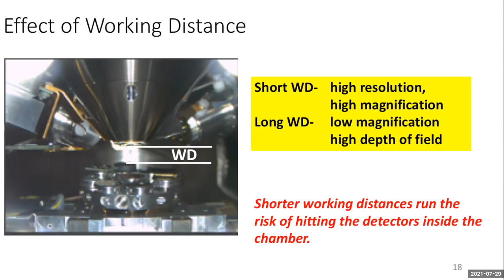However, a shorter working distance may run the risk of hitting the detectors. You can see the detectors inside the chamber of the SEM. So a shorter working distance may cause the sample to hit the detectors inside the chamber. So be careful when you work with a short working distance.